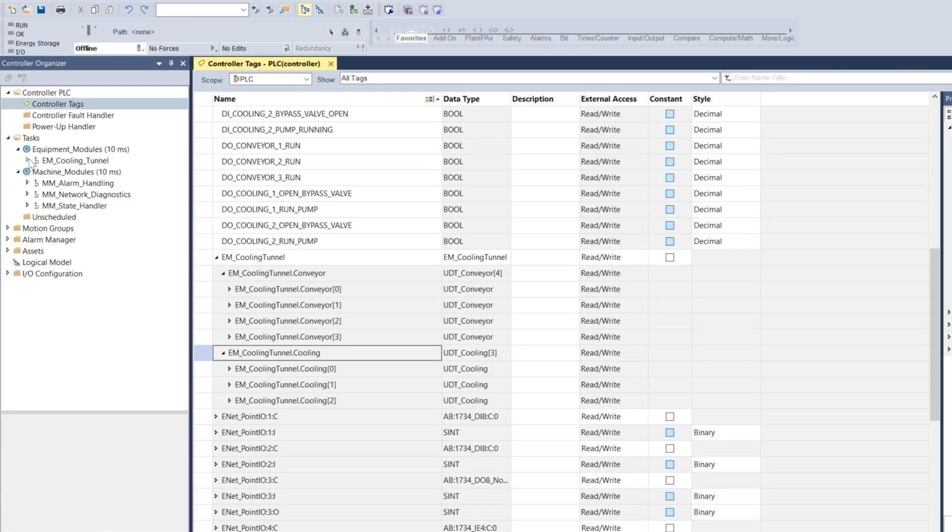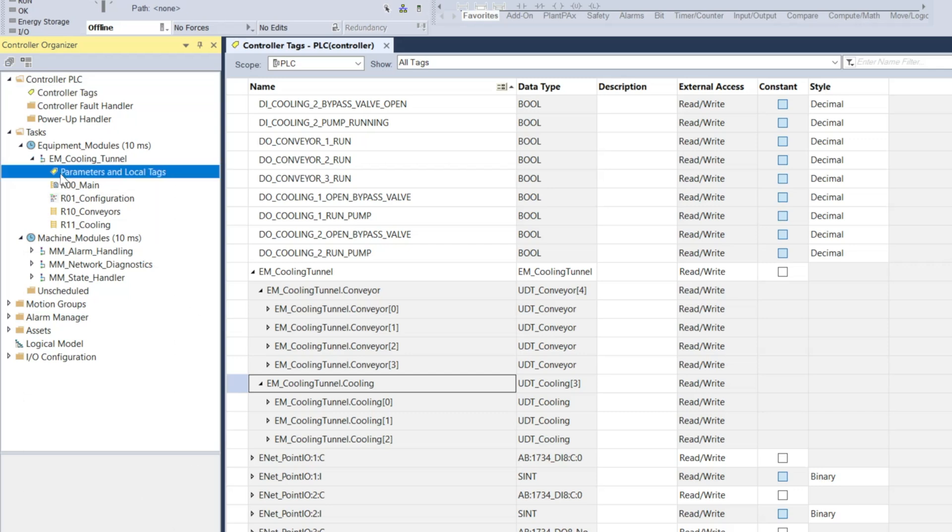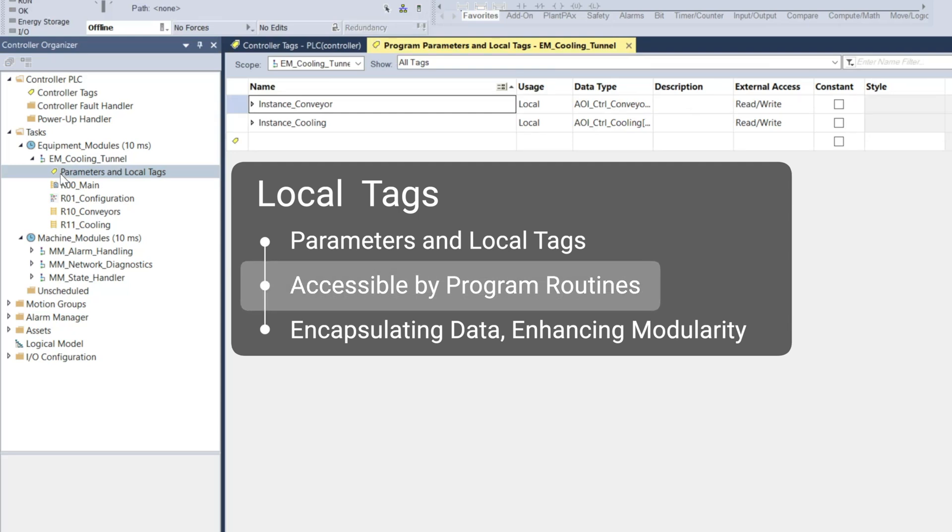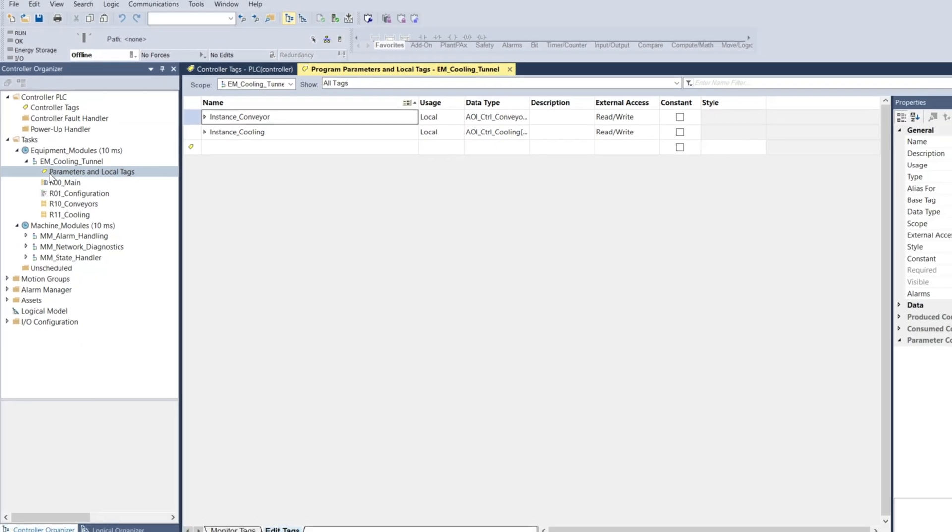Local tags are defined in the parameters and local tags section of a specific program in studio 5000 and they are accessible only within the routines of that program. They are typically used to encapsulate data specific to the program's operations, enhancing modularity and making management tasks such as copying and pasting programs more efficient.